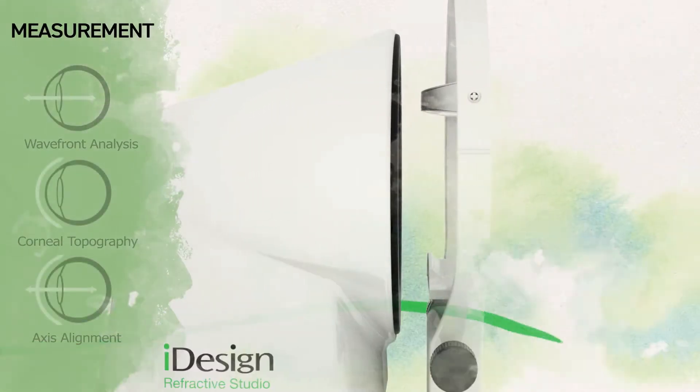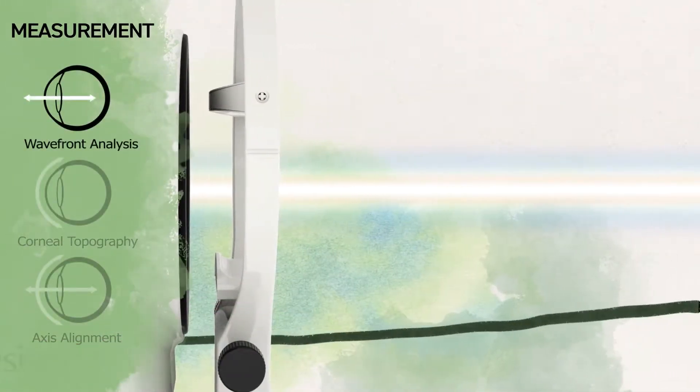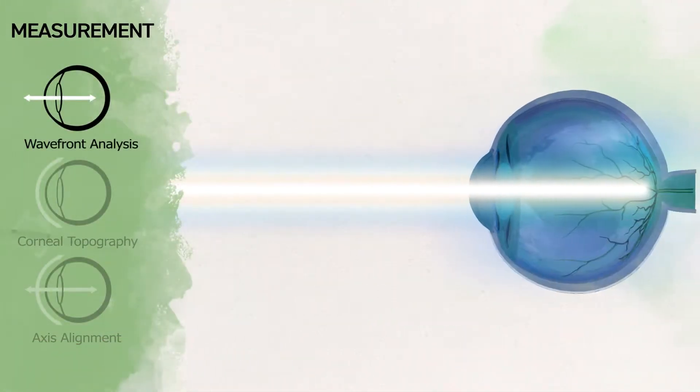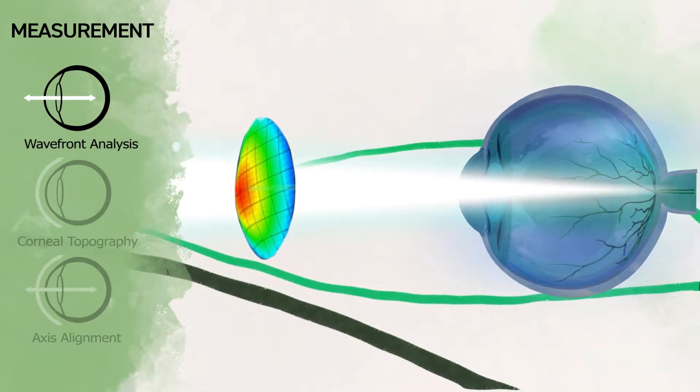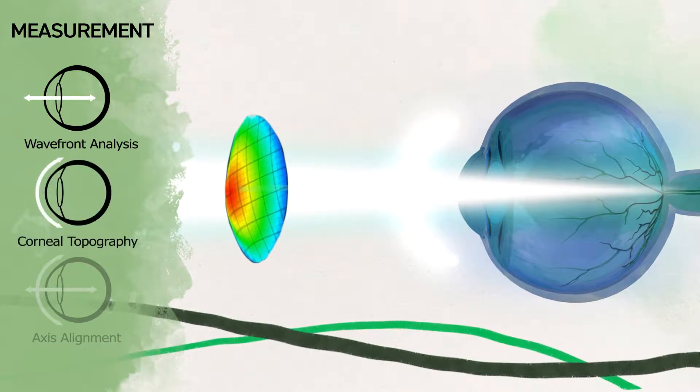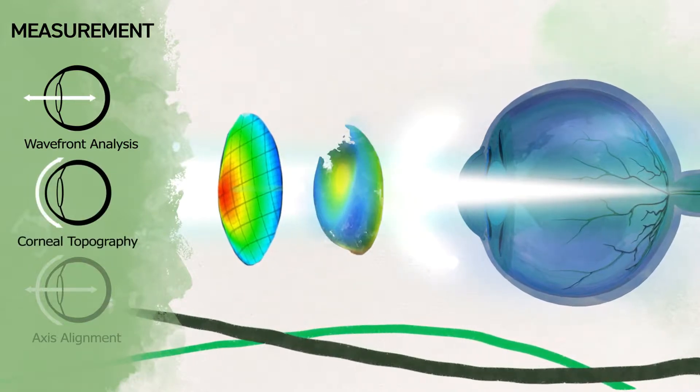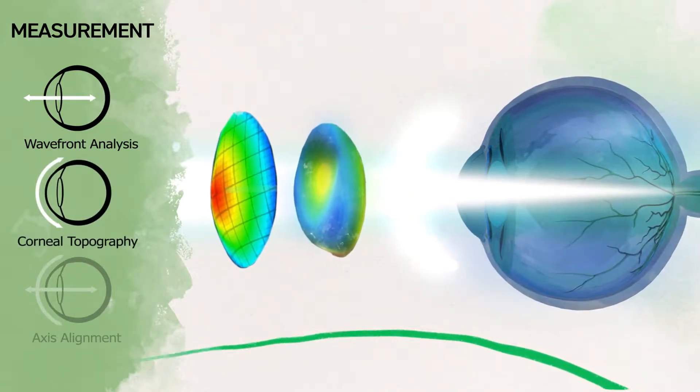To do this, the system projects a single spot of light onto the retina, capturing and analyzing the reflected light using over 1200 sensors across the pupil, while simultaneously analyzing the corneal surface using a highly advanced full gradient corneal topographer.